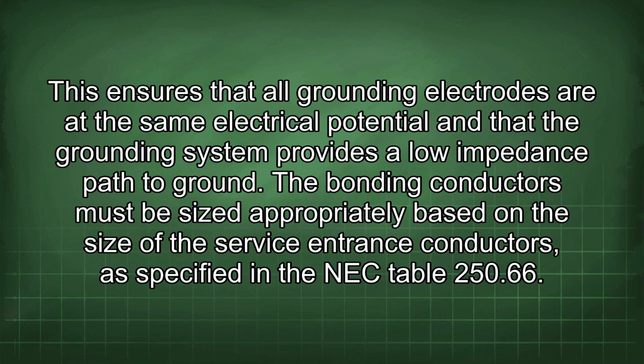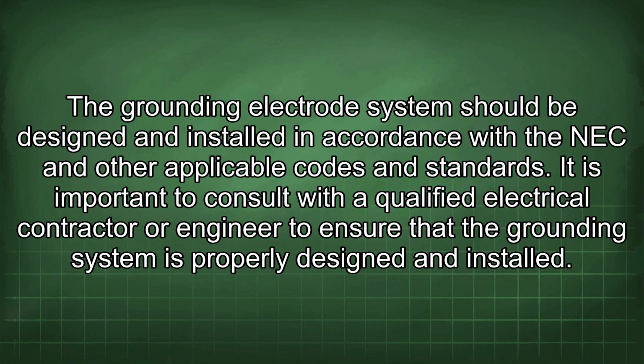This ensures that all grounding electrodes are at the same electrical potential and that the grounding system provides a low impedance path to ground. The bonding conductors must be sized appropriately based on the size of the service entrance conductors, as specified in the NEC Table 250.66.